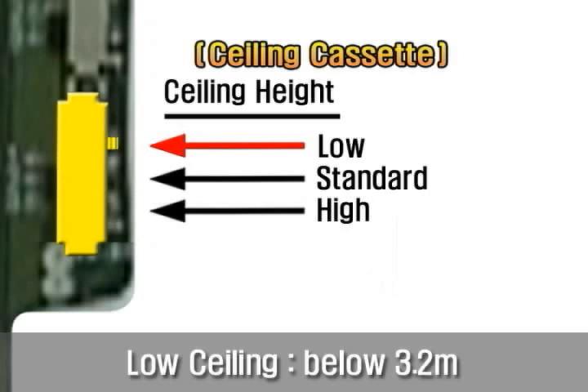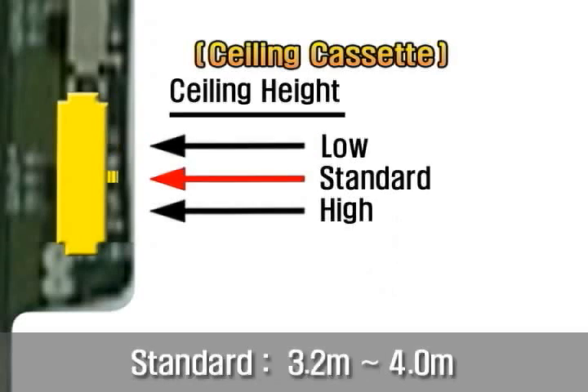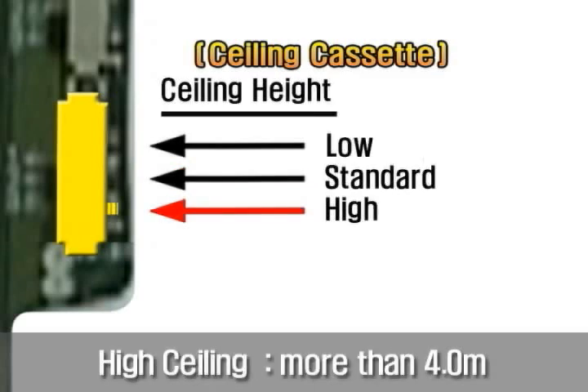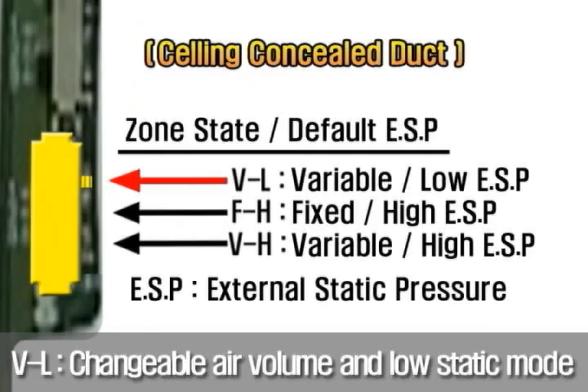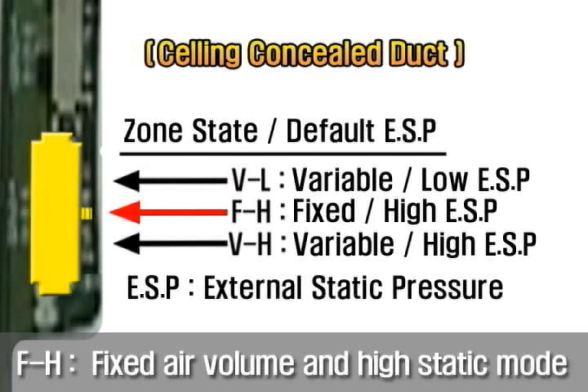When selecting ceiling height for ceiling cassette, the low is for the height of below 3.2 meters with decreasing air volume. The standard is between 3.2 meters and 4.0 meters without change in air volume. The high is over 4.0 meters with increasing air volume. In ceiling concealed duct, choose the selection switch of zone and default external static pressure like these. V-L is for the changeable air volume and low static mode. F-H is for fixed air volume and high static mode. If it has a zone controller, fan speed doesn't change for the damper operation.